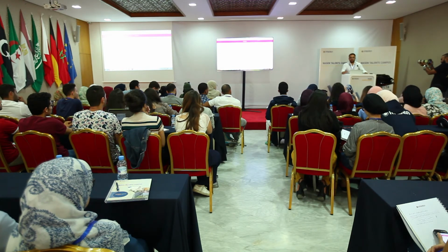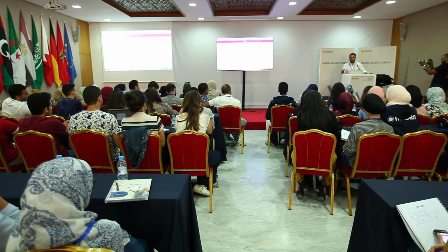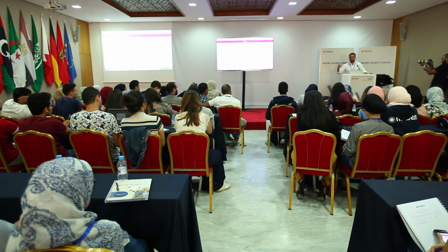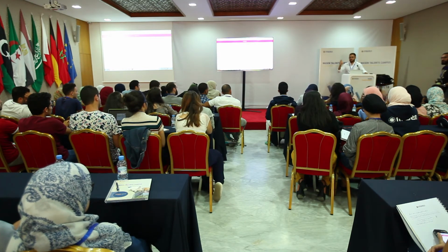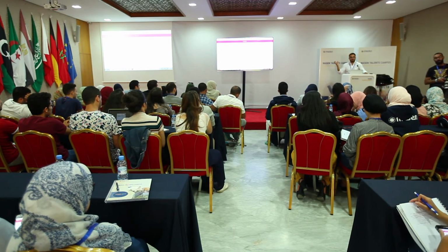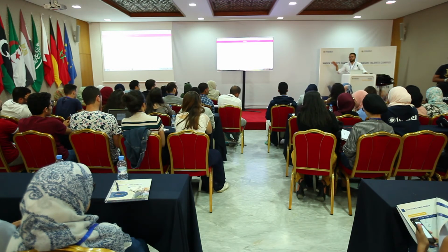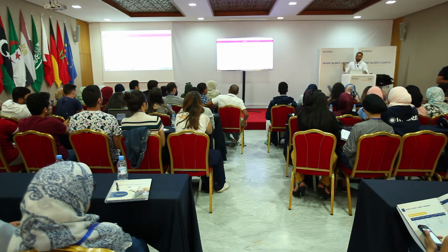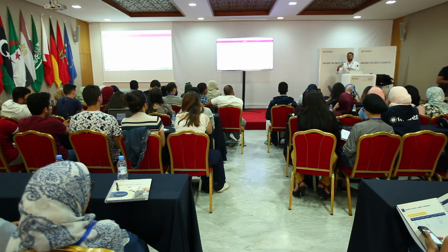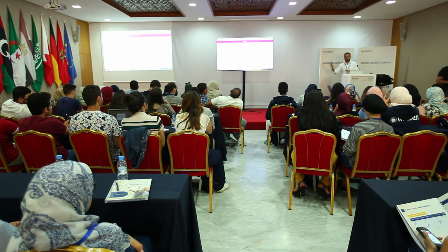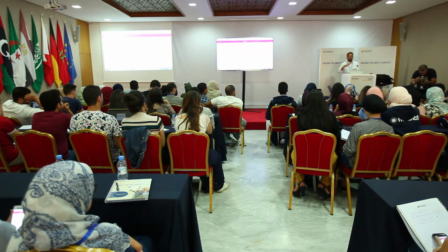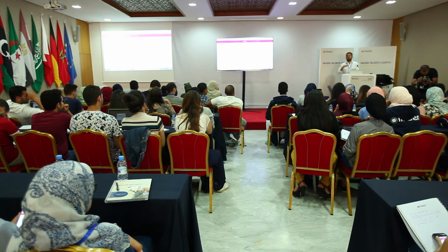Why, when you optimize the IRR, does the storage capacity decrease? Well, it depends. In that example, the price was increased by 3 only during the 3 hours in the evening. So if you're paid 3 times more in the evening, the IRR shows that the best plant is the one that only provides energy during those 4 hours. So it's a small storage plant, in terms of hours, not necessarily in terms of energy. But if you were paid the same throughout the day, most likely the most profitable plant is not one with 4 hours, but one with 10 or 12 hours of storage.